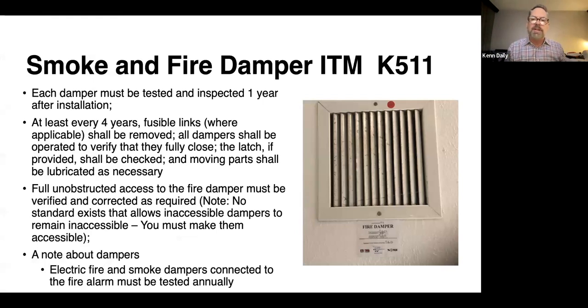And then, of course, subsequent to that, whether it's KTAG 521 or KTAG 511, you have your dampers inspected. Now, dampers are inspected 1 year after installation, and then every 4 years after that. And again, every 4 years, they're cleaned. So they're cleaned, oiled, lubed, and they make sure they fully close and latch. And then, of course, it's really important for you to know whether it's a fire damper or a smoke damper. Smoke dampers are actually part of your fire alarm system.